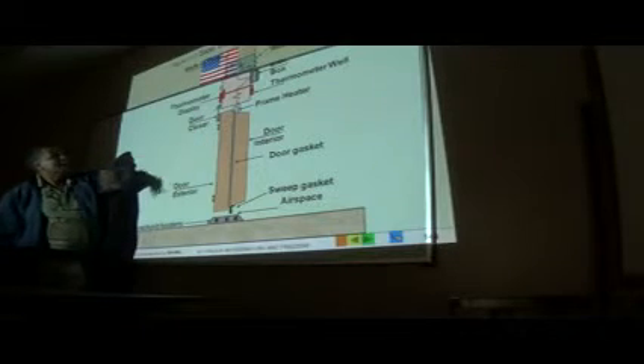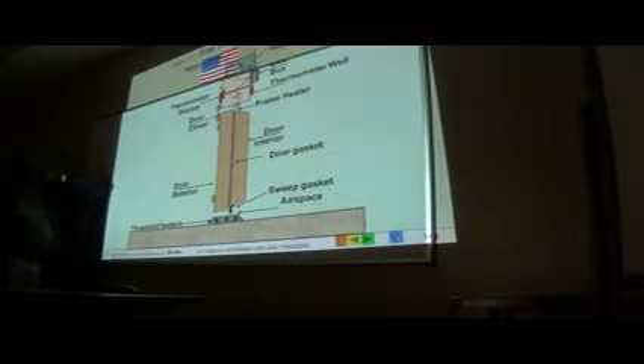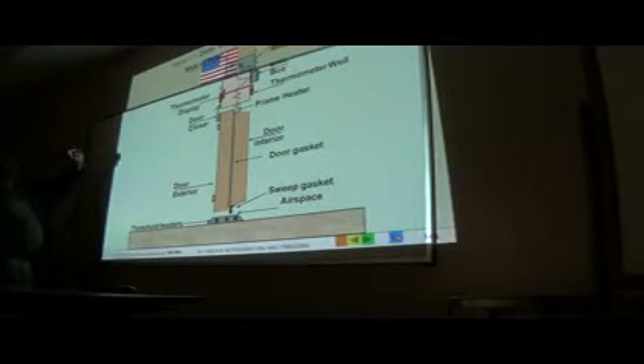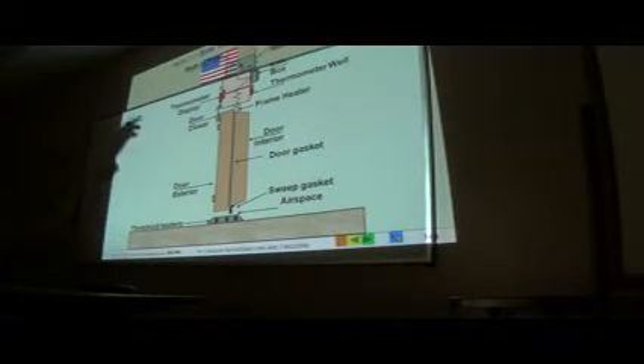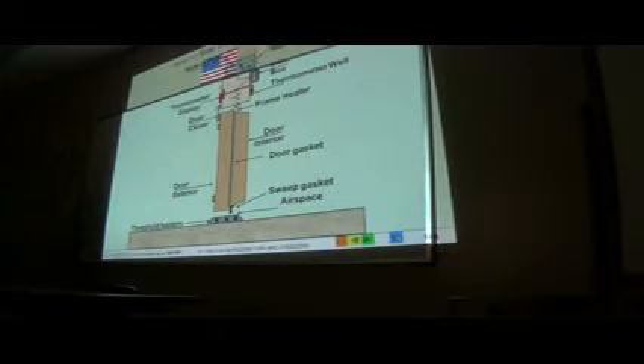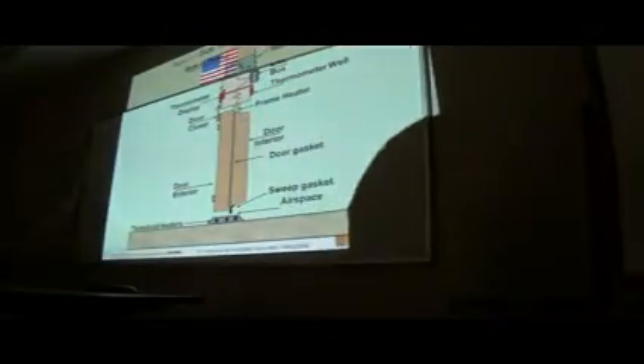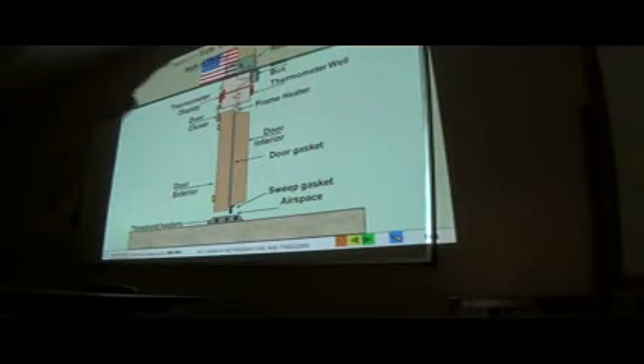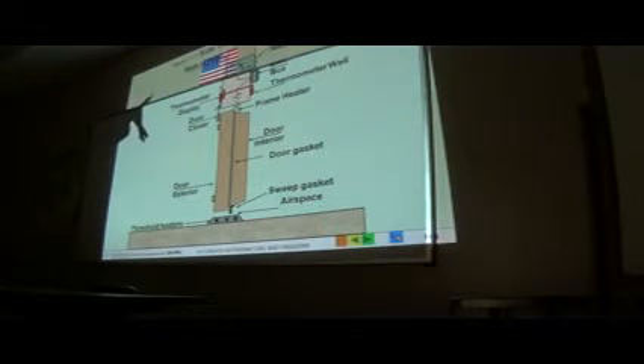That's my door closer, and where's my pressure relief port? Right up top. There's always a pressure relief port, and in some cases it's heated. Because what happens if I close a freezer door and don't have that port: the door can pop back open, number one. And if you do get it closed, the pressure differential will keep it shut, so when you go to open it, you can't, because the pressure from outdoors pushes against that door. So the equalization port allows the two pressures to equalize so you can open the door without breaking your back.